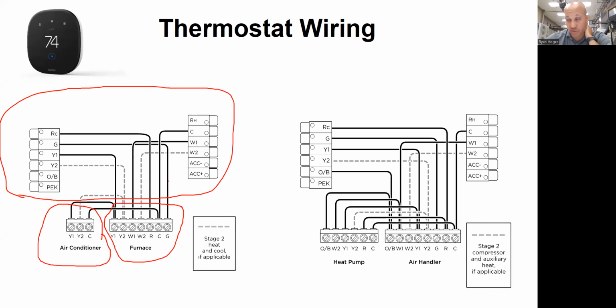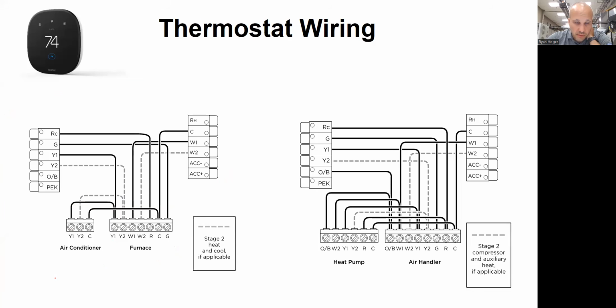So I have thermostat wire connecting those three things. Your house is the same way. Your thermostat wires back to your furnace or air handler, and your furnace or air handler wires to your condensing unit or heat pump outside, right? There we go. All right. So we got all those pieces there. So what those guys do, each of these wires has a job.